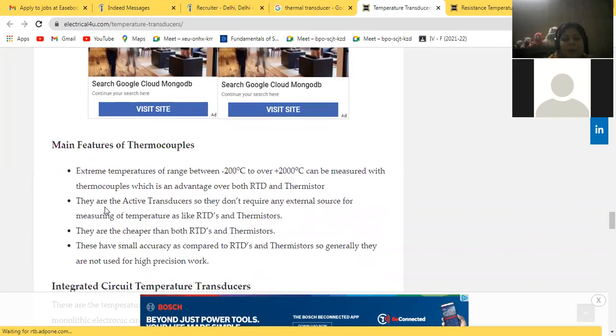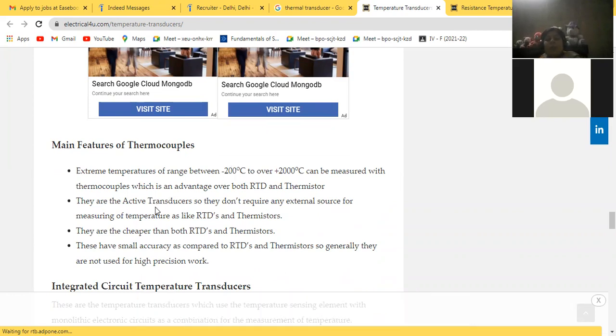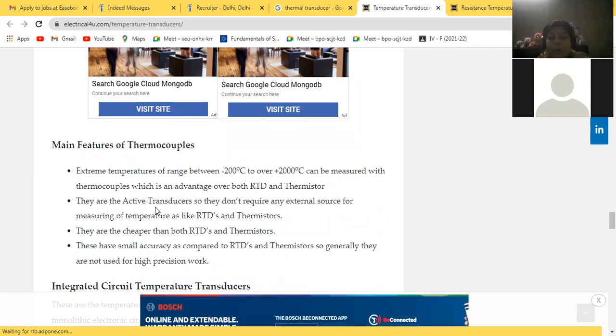The main features of thermocouples: extreme temperature range between minus 200 degree Celsius to over 2000 degree Celsius, because both cold and hot junctions can be measured with a thermocouple, which is an advantage over RTDs and thermistors. They are active transducers, so they don't require any external source for measuring temperature, unlike RTDs and thermistors. They are cheaper than both RTDs and thermistors, but have smaller accuracy compared to RTDs and thermistors, so generally they are not used for high precision work.